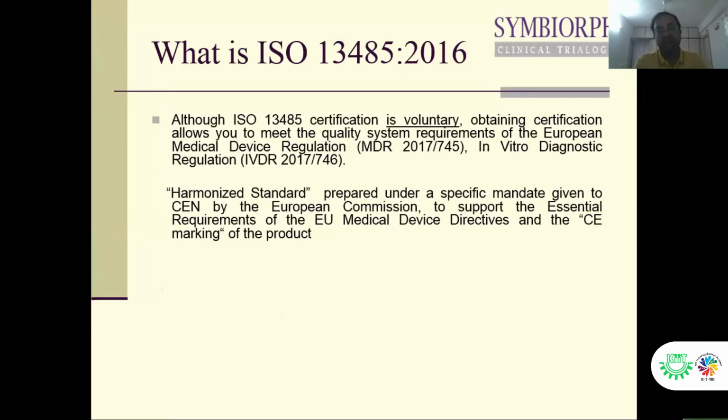So 13485 is a voluntary certification. It is not mandatory in general, but for any medical device manufacturer who wants to sell their product in India as per the Indian Medical Device Rules 2017, or who intends to sell in regulated countries and obtain CE certification as per MDR 2017/745, or for in vitro diagnostics, IVDR 2017/746, the implementation of 13485 becomes mandatory.